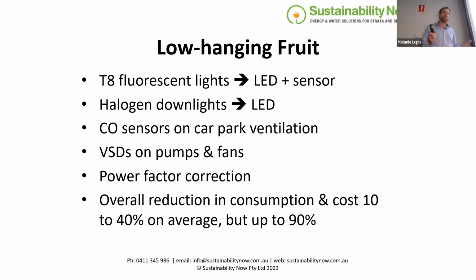Power factor correction. I haven't done a power factor correction unit in a while. So power factor affects your peak demand charges if you're on a demand tariff. Any buildings that use over 100 megawatt hours a year will probably be on a demand tariff.